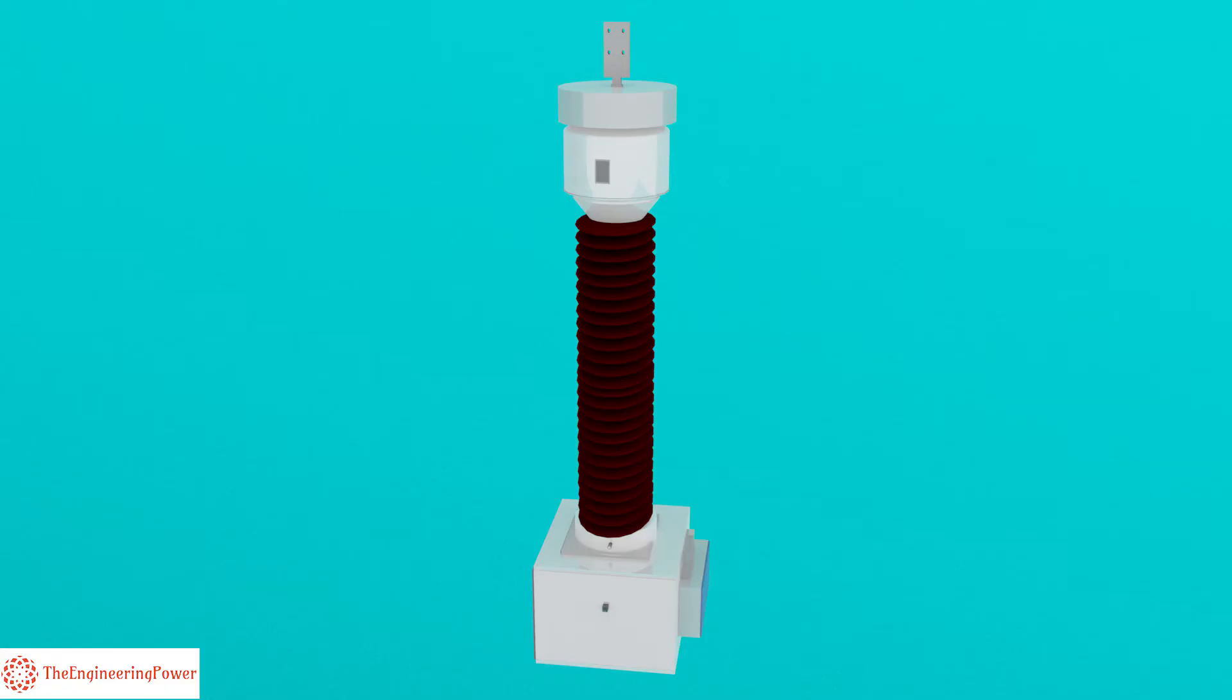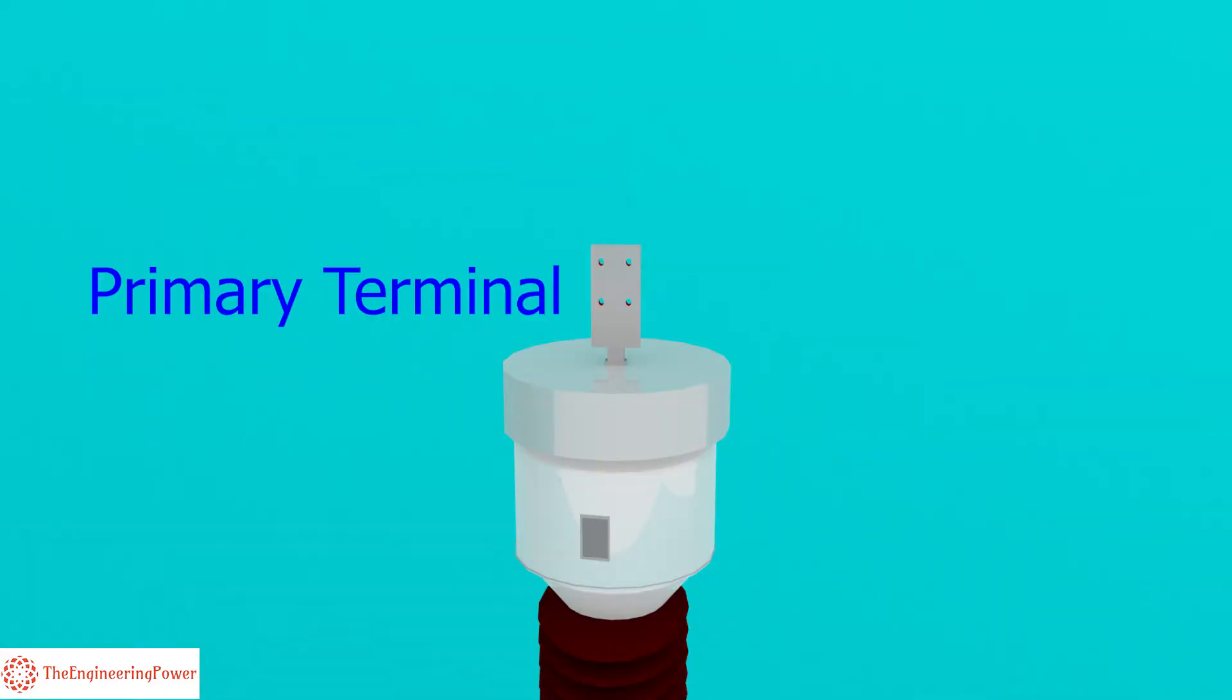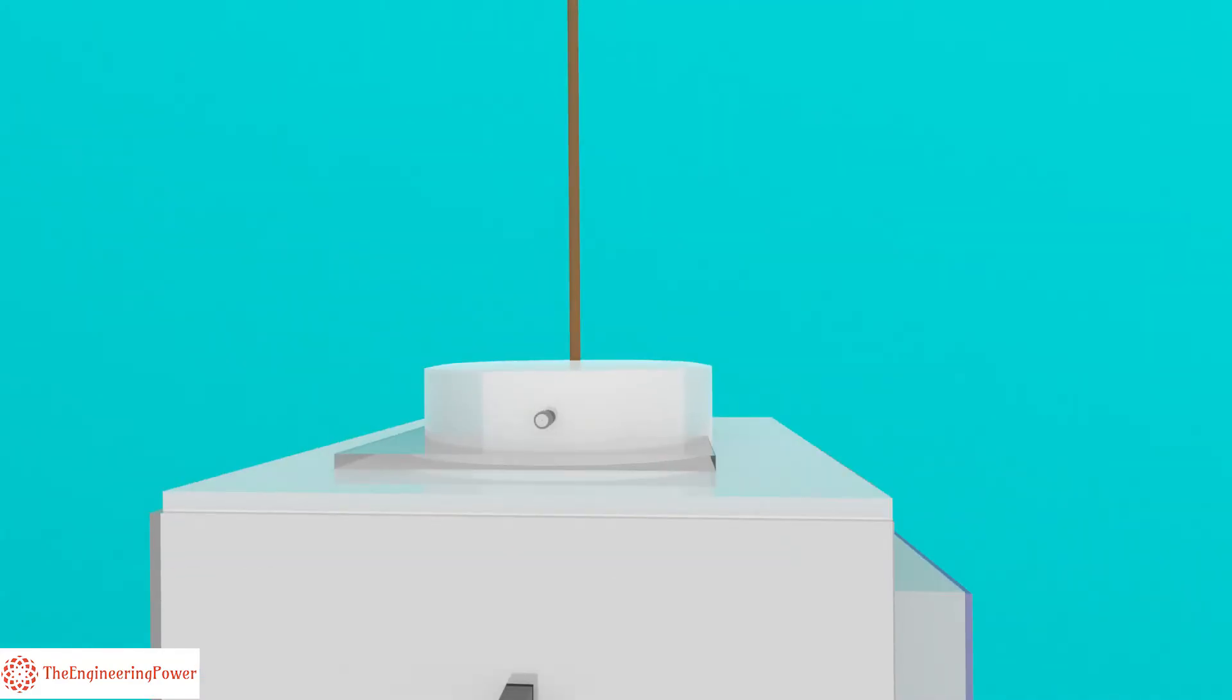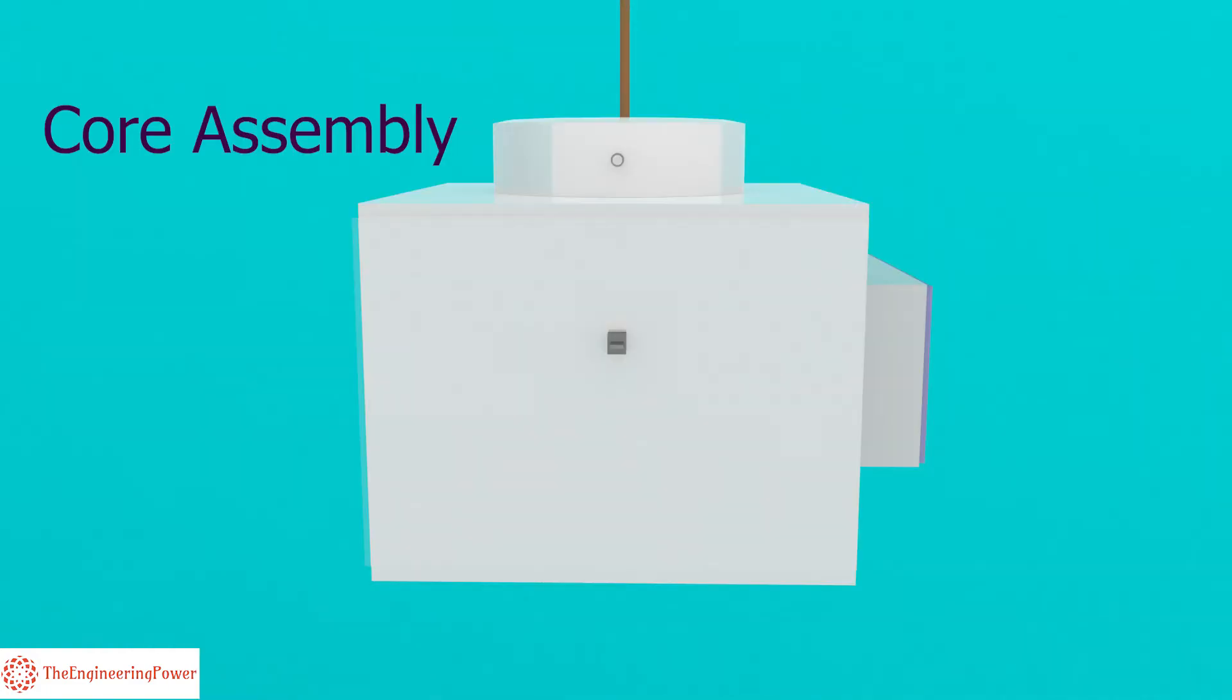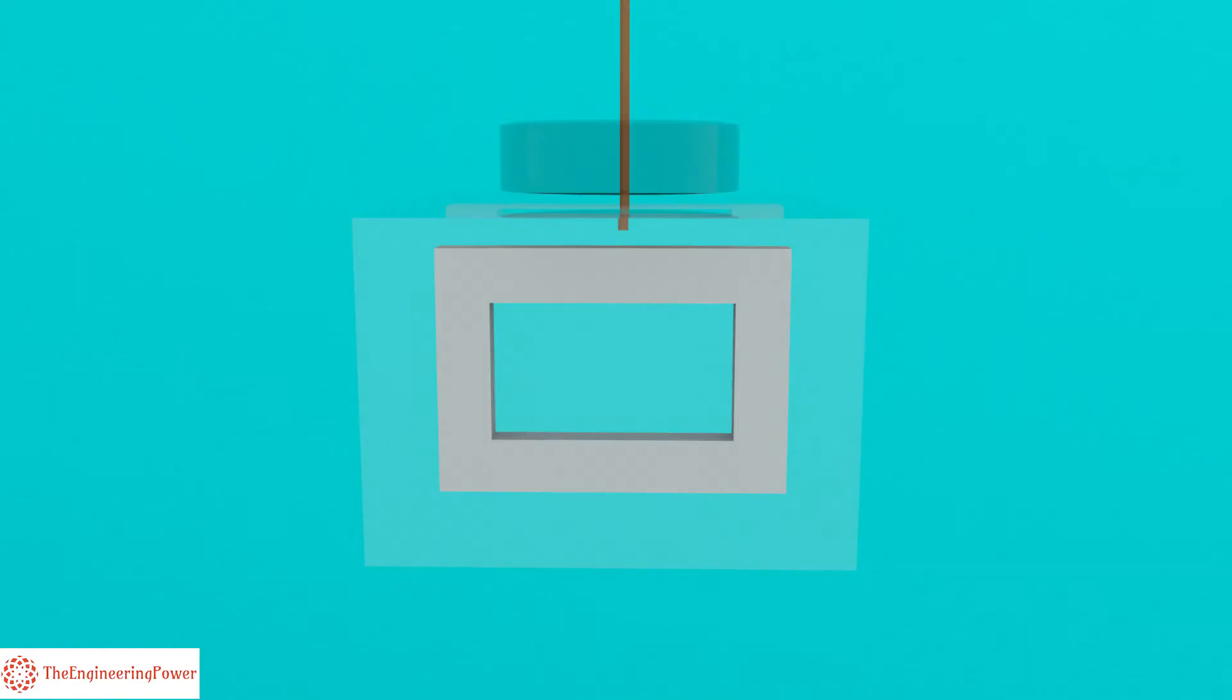That's how a PT looks like. That's the primary terminal of PT which is connected to the main power line through a dropper. A high power capacity conductor connects the primary terminal with the PT compartment at the bottom. In the bottom compartment the main core assembly is installed.